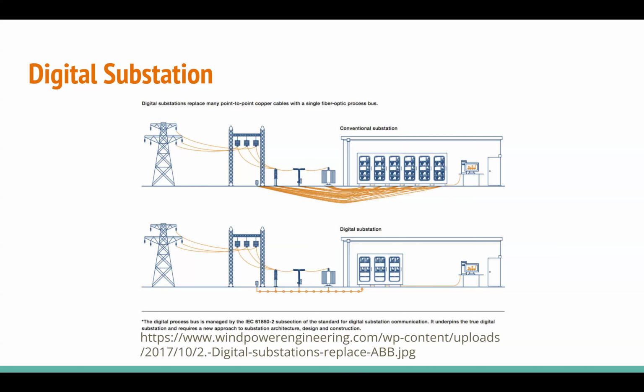The difference with a digital substation, what we're looking at here, is that instead of taking the secondary values back from the equipment, like the CTs and VTs, into the control house with hardwired signals, we convert them into digital signals out in the yard and then bring back digital information into the control house.